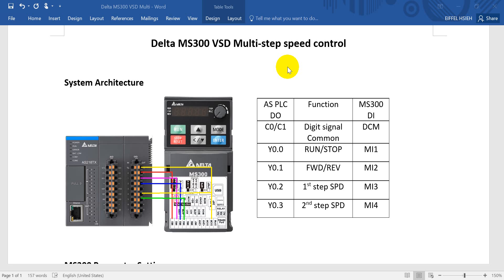We link the AS PLC to the MS300 digital input. For the inverter digital input, we call it a multi-function input, defined as MI1. C0 and C1 are the digital signal common. Y0.0 from AS PLC means run and stop, Y0.1 means forward/reverse, Y0.2 means first step speed, and Y0.3 means second step speed.